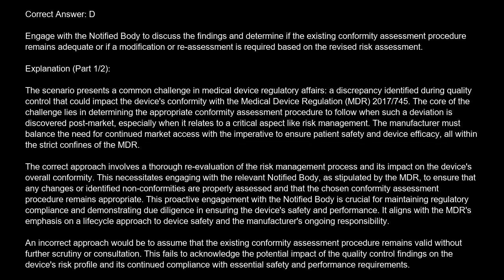The correct answer is D. Engage with the notified body to discuss the findings and determine if the existing conformity assessment procedure remains adequate or if a modification or reassessment is required based on the revised risk assessment. Explanation. The scenario presents a common challenge in medical device regulatory affairs, a discrepancy identified during quality control that could impact the device's conformity with the Medical Device Regulation, MDR 2017/745. The core of the challenge lies in determining the appropriate conformity assessment procedure to follow when such a deviation is discovered post-market, especially when it relates to a critical aspect like risk management.